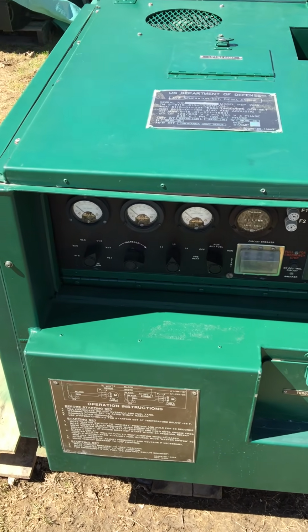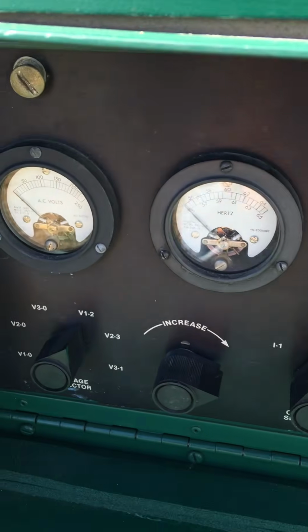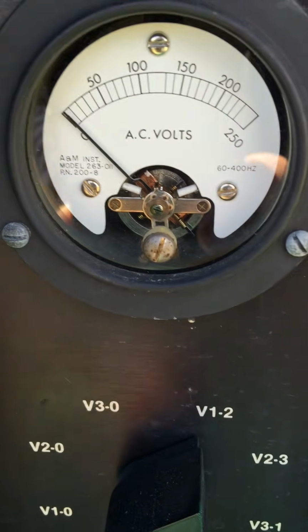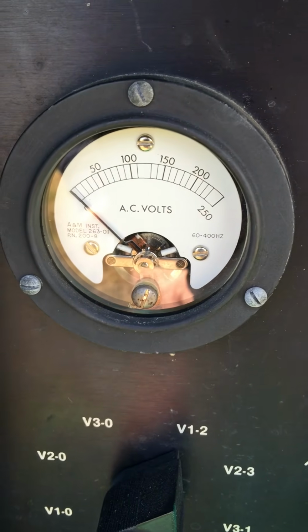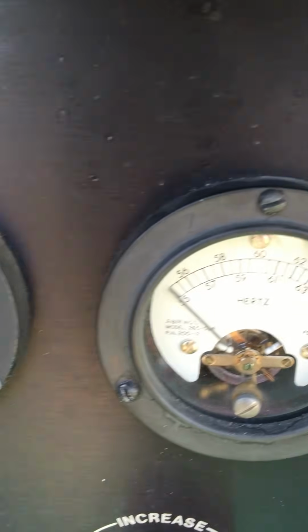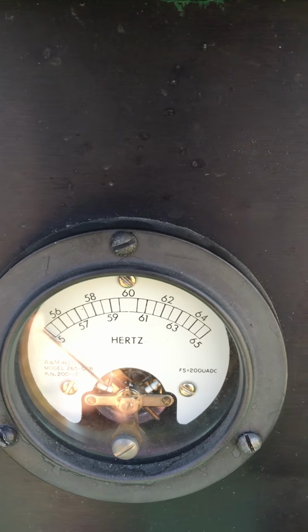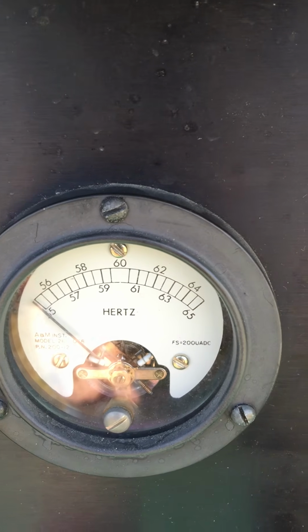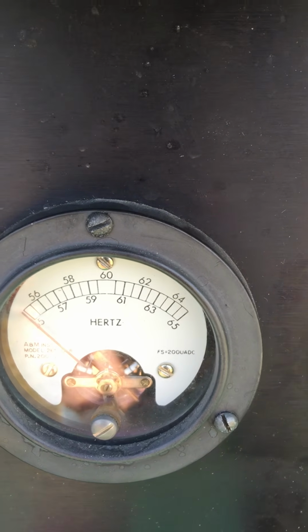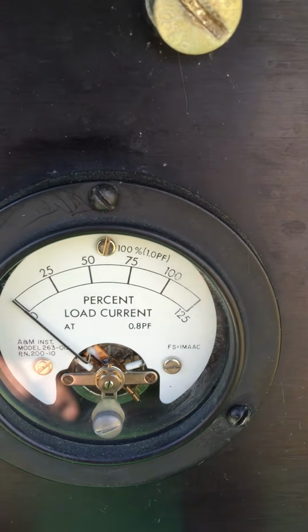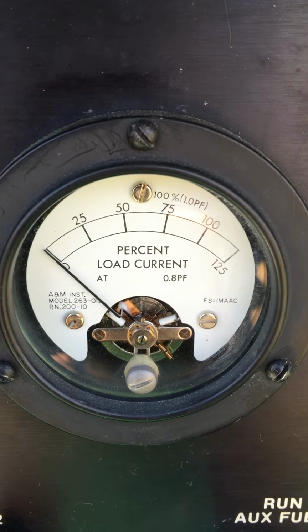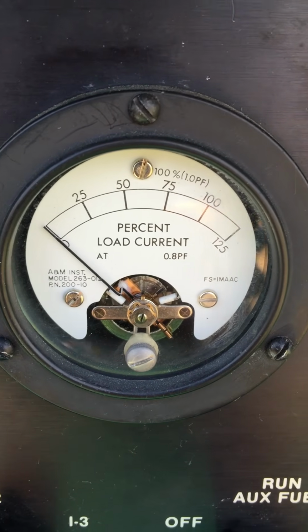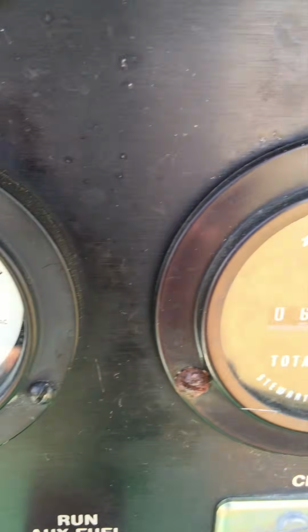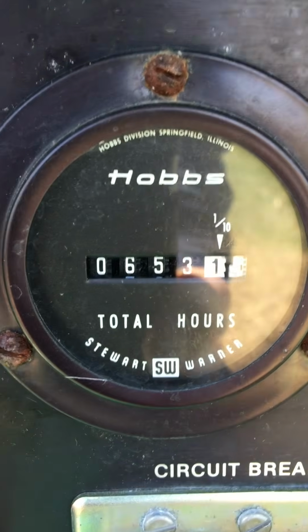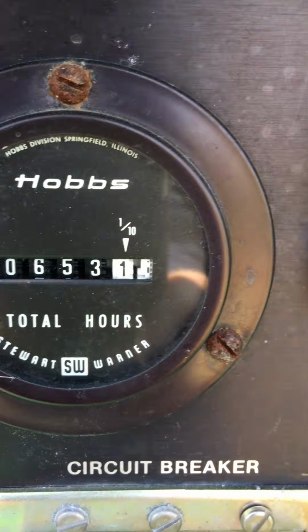First I want to come in, show you the meters and switches here on the front. Here's your voltage, your AC voltage. Coming on over is your hertz. We like to see them set at 60 to 61 hertz to start with, and then you load it. Want to maintain it near that 60 hertz. This is the percent of load meter, and you'll see that needle move as I load the set. This particular unit has 653 hours on it.